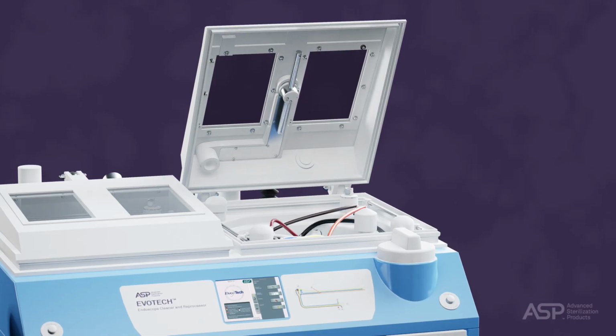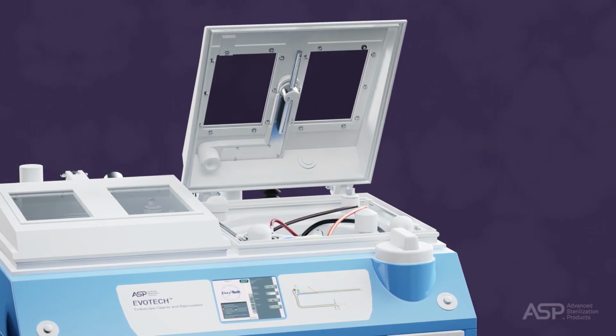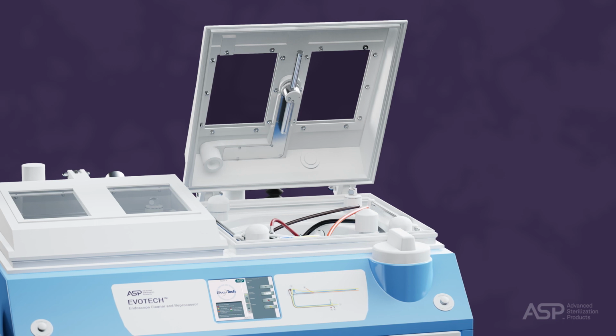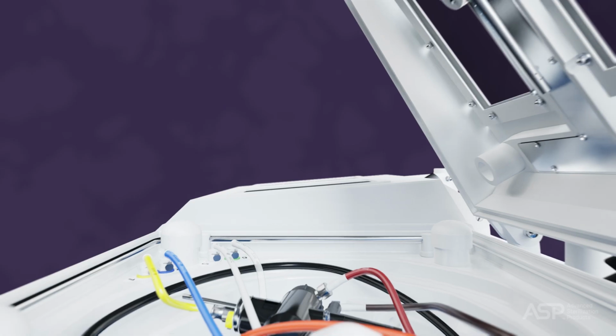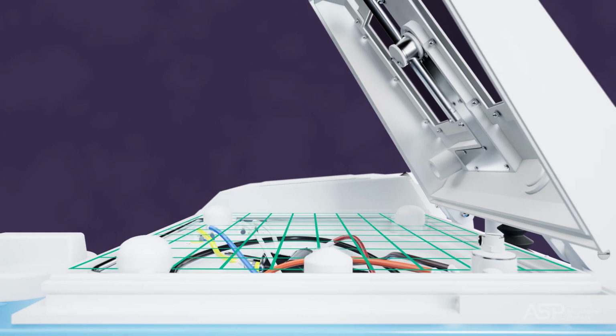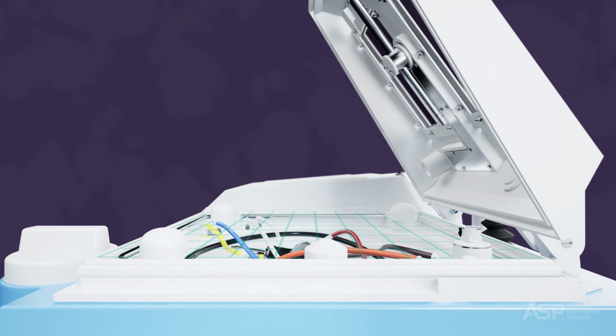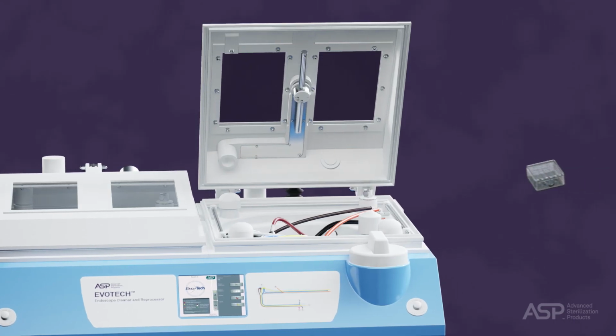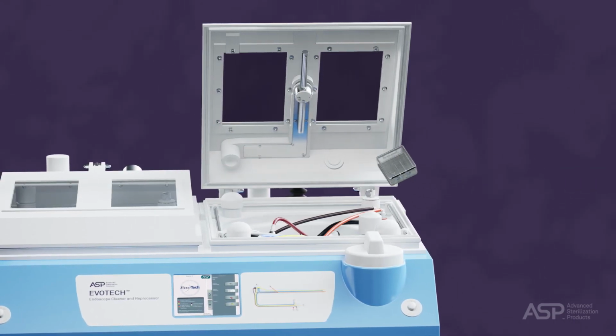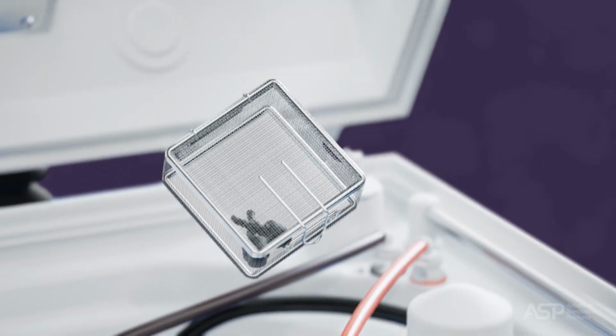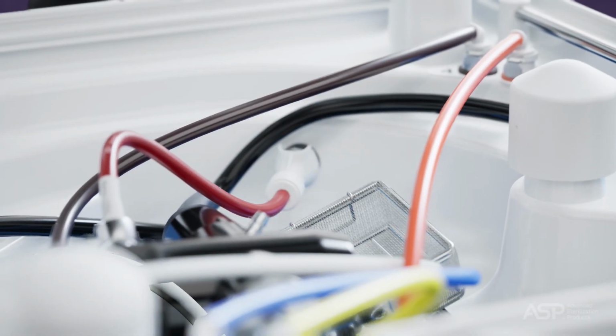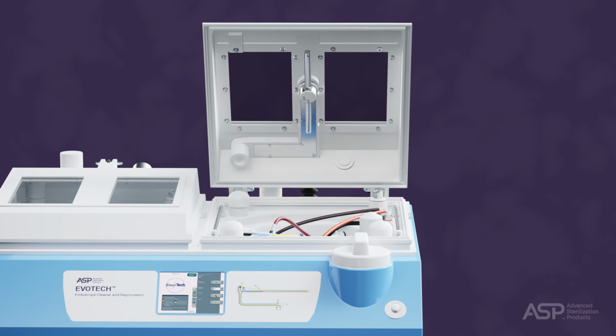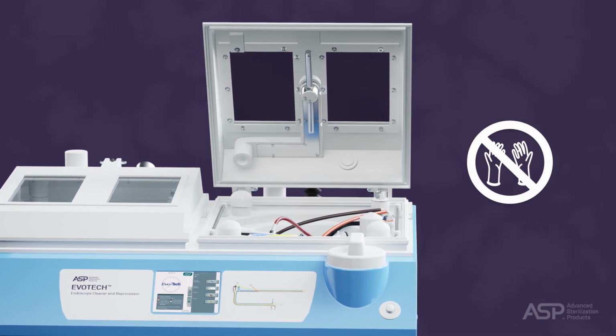Check to ensure the connectors are placed in a way that will prevent them from being caught in the spray arm when the lid is closed for processing. The connectors should be lower than the metal bar that encircles the basin. Place any small endoscope accessories, such as the water suction buttons, in the metal mesh basket and place in the basin. After proper placement of the endoscope and connectors, remove contaminated gloves.